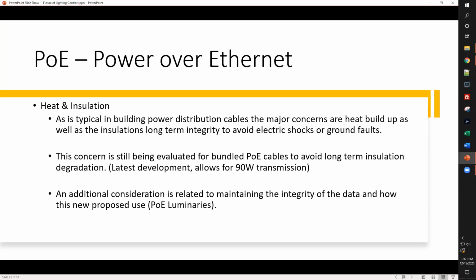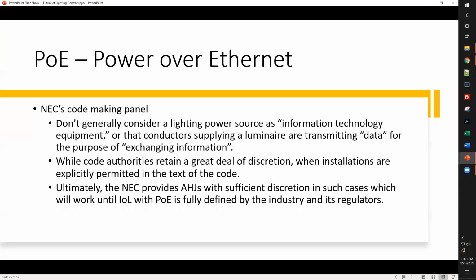Additional consideration relates to maintaining the integrity of the data in this new proposed use for Power over Ethernet luminaires. The NEC's code-making panel doesn't generally consider a lighting power source as information technology equipment. They don't think you're going to be sending a signal or downloading something from your lighting fixture, or as they define it, for the purpose of exchanging information.